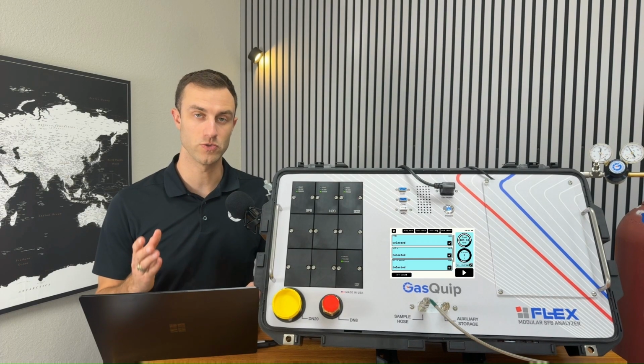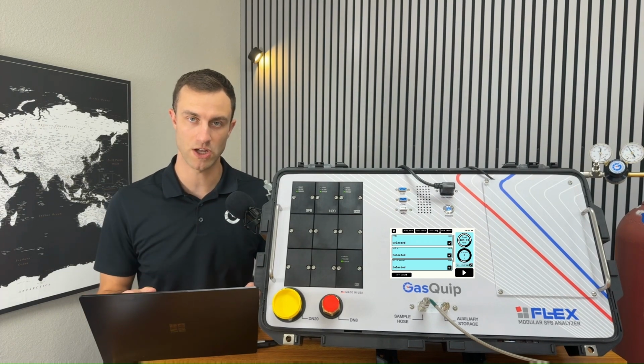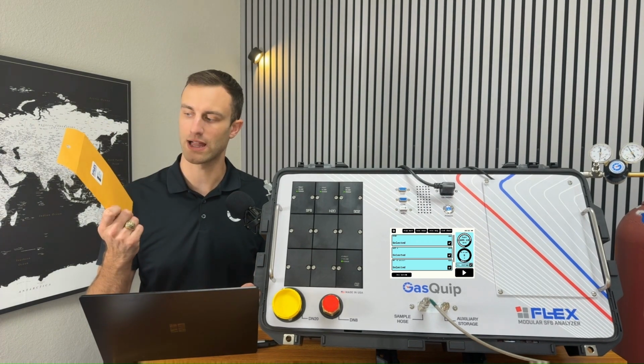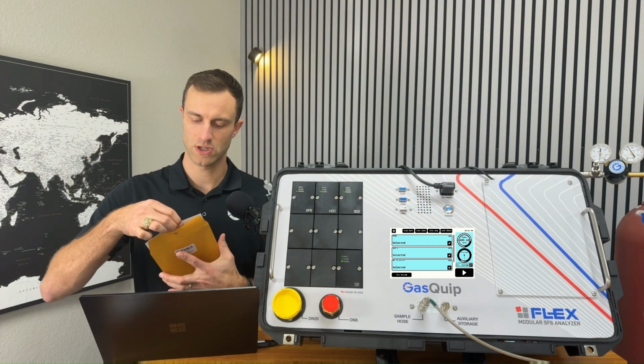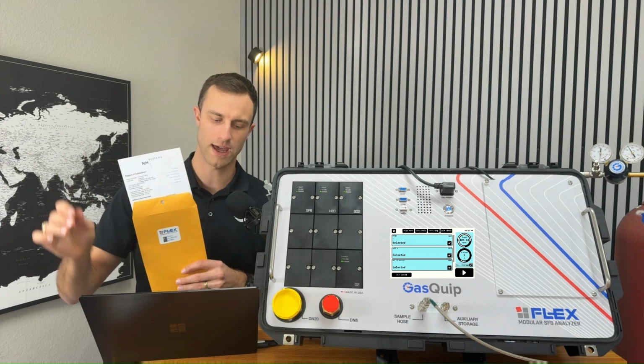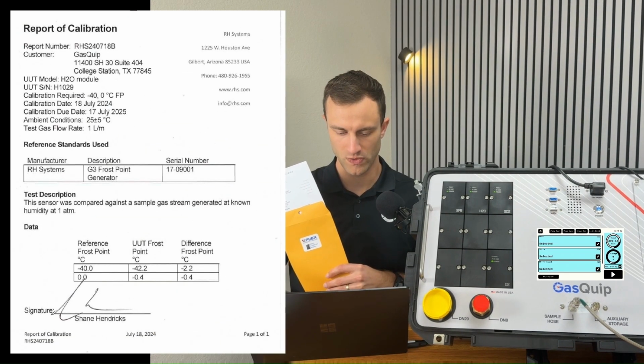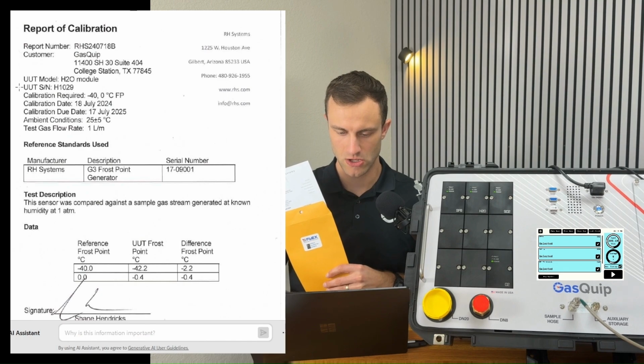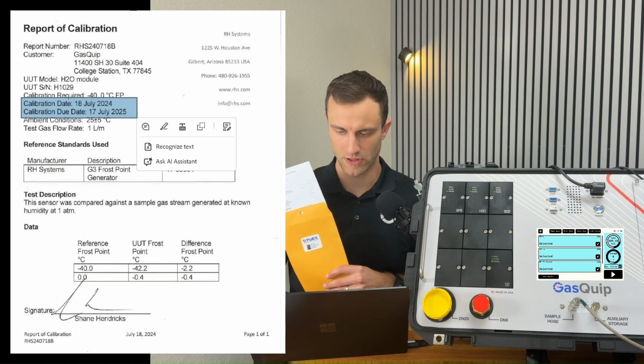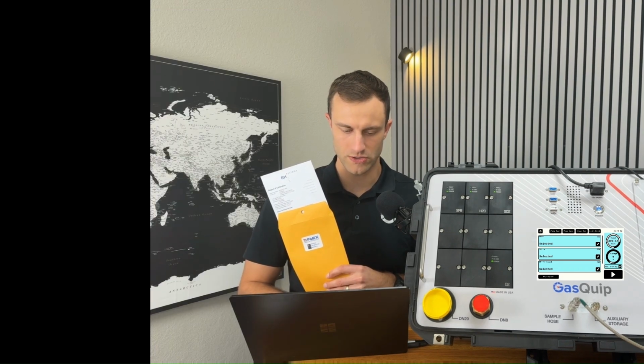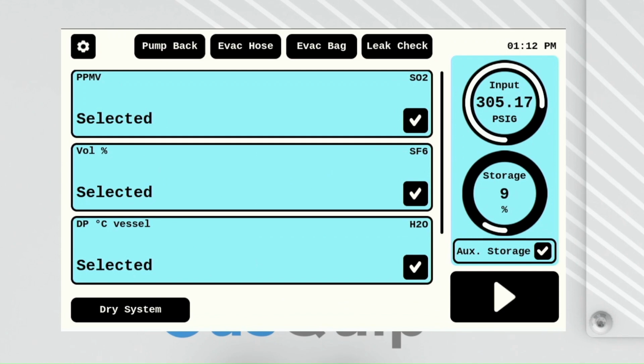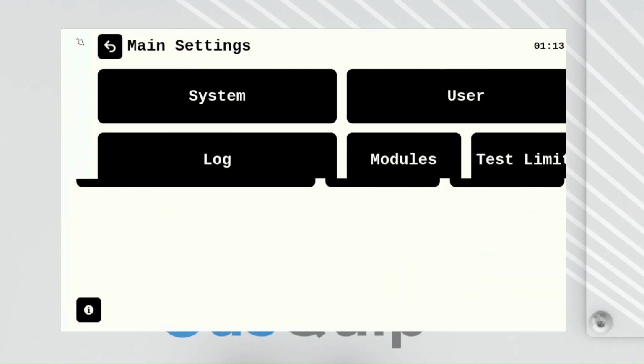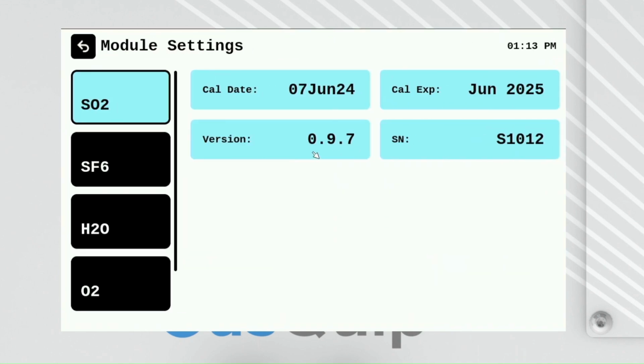There are two different ways to check the calibration status of your individual modules. The first is to look at your calibration reports for each of the modules, and you just pull that out and look at that, and we can look at the close-up of it. So here on the calibration certificate, you would look at the calibration date and the calibration due date there. And also we can go into our settings here in the top left and go to modules. Click in on any of the individual modules, and you're looking at the calibration date and the calibration expiration date.